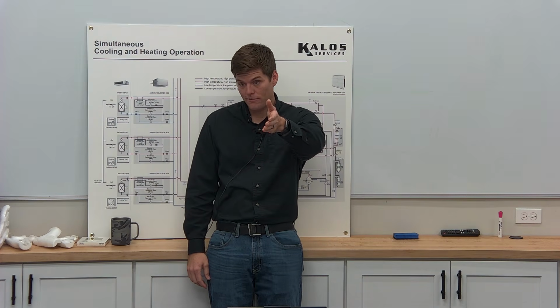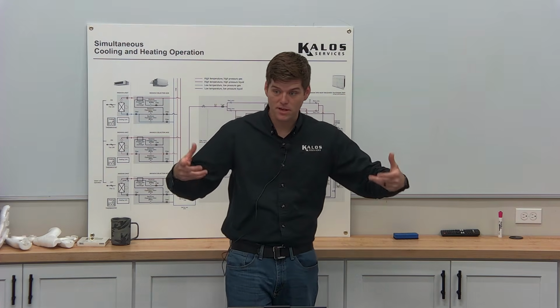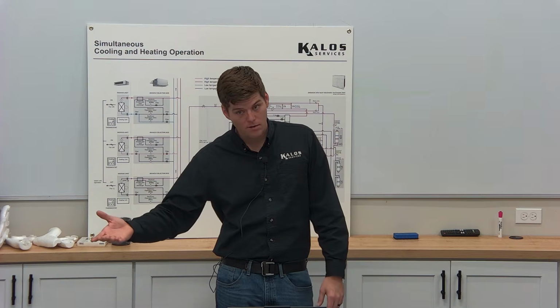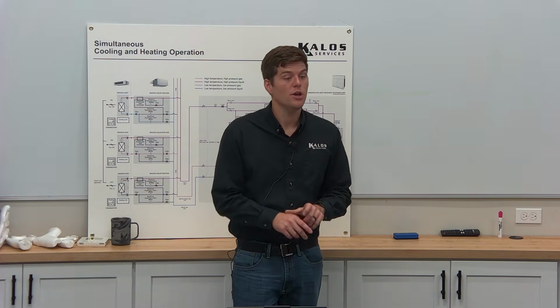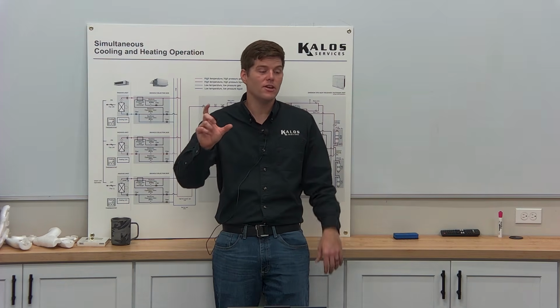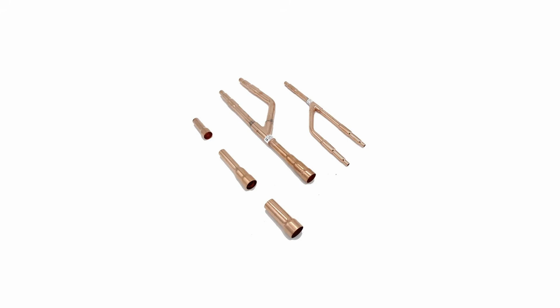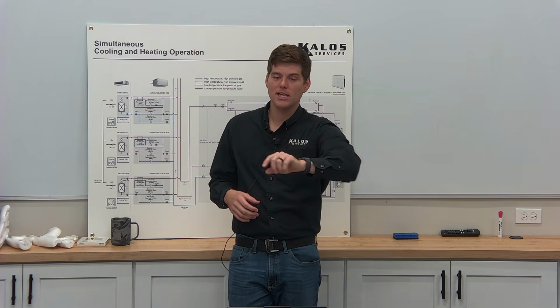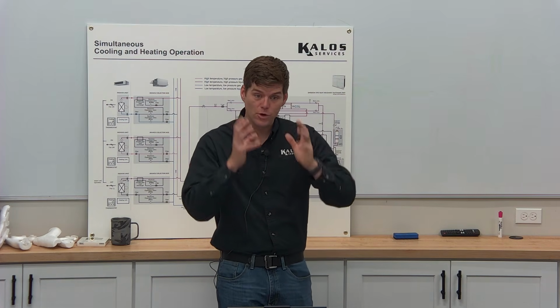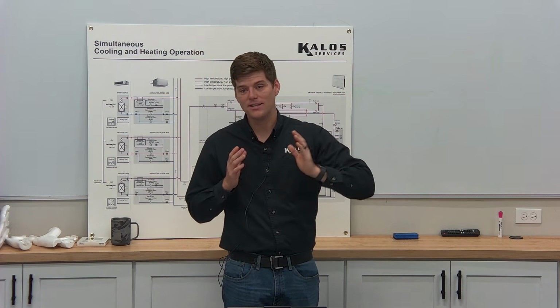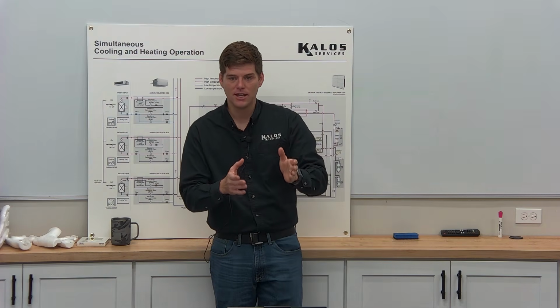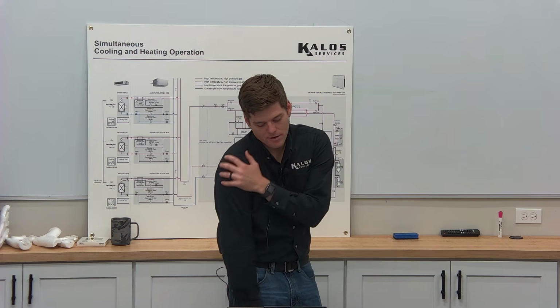That's a small indoor Refnet kit. You'll notice that every Refnet kit has a specific model number with a specific number in that model number to tell you what size piping it's rated for. You'll pull out the installation manual of that and it'll tell you. It even comes with little actual copper reducer pieces to upsize it, to downsize it. It's all designed to ensure that no matter where in the system this fan coil lands, let's say it's a 3-ton at the very end, that the piping has been sized correctly to ensure that at a full demand load on that unit, I can still deliver 100% capacity at any given time, and that I'm not restricted. Why does that matter when we talk about those?